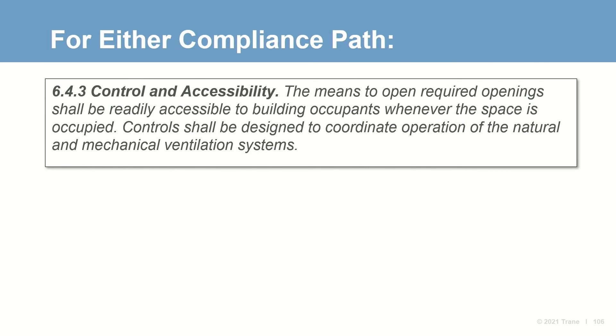Finally, for either compliance path, the means to open natural ventilation openings must be readily accessible to the occupants, and the controls must properly coordinate operation of the natural and mechanical ventilation systems. That covers the three ventilation procedures: the ventilation rate procedure, the IEQ procedure, and the natural ventilation procedure.